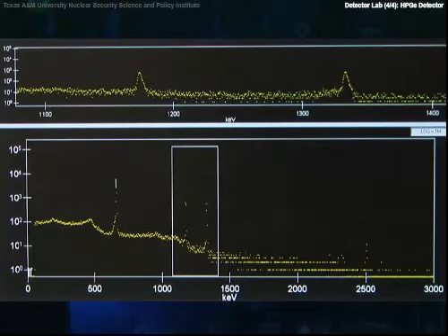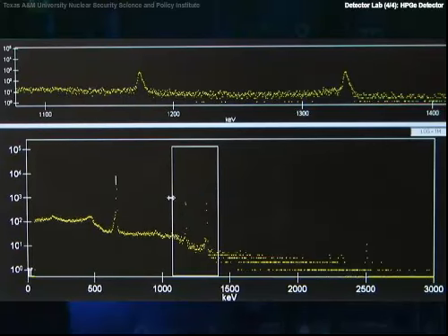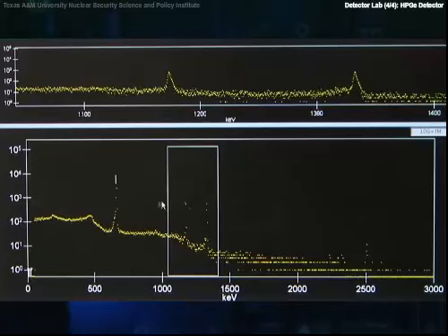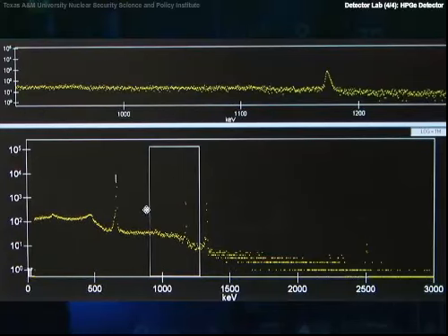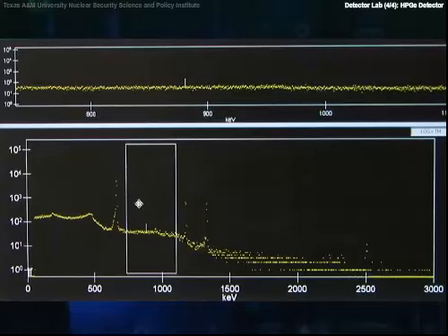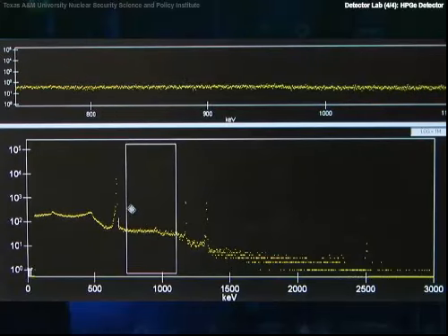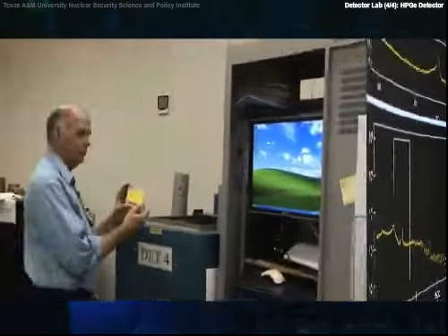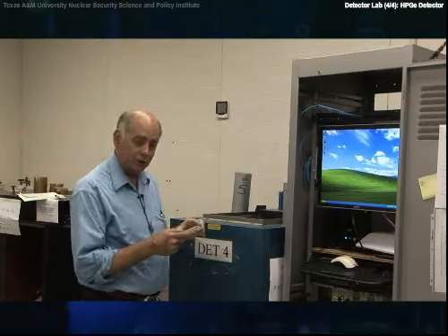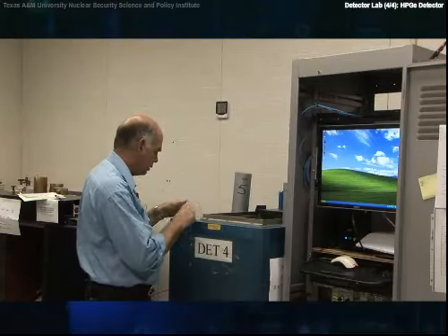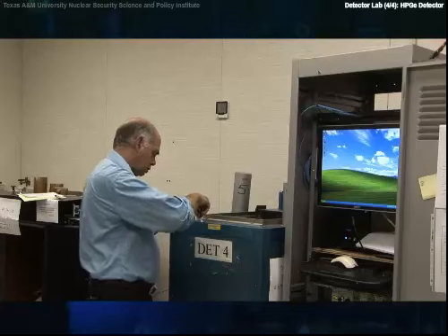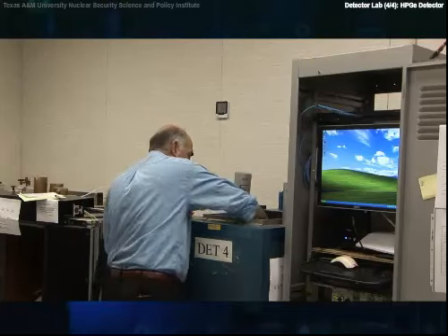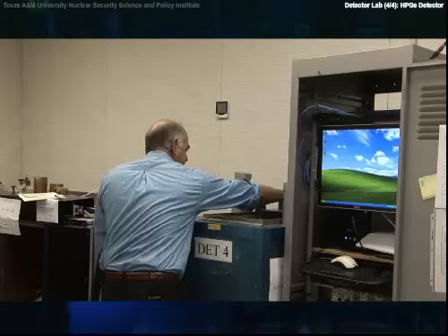To construct our absolute efficiency calibrations, we're not going to use these check sources. We have a europium NIST traceable source, and we're going to put that in, and then we can construct the absolute efficiency of our detector for stand 3. Here's our mixed gamma NIST traceable source. Being careful to add it in the same geometry.